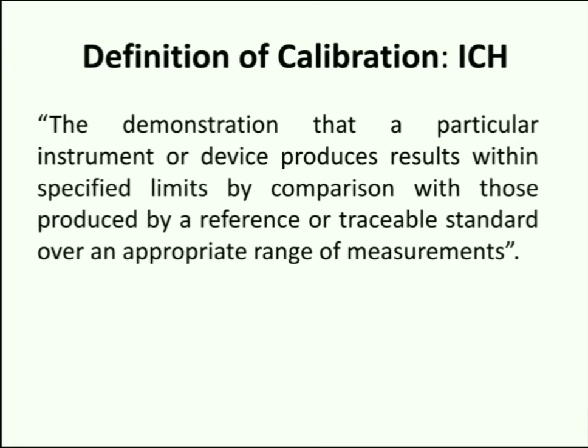So according to ICH, calibration is the demonstration that a particular instrument or device produces results within specified limits by comparison with those produced by a reference or traceable standard over an appropriate range of measurements. This definition means that, according to ICH, calibration is the demonstration of whether a particular instrument or device produces results within the specified limits or not. Also, the data obtained is verified by comparison with the data from a reference standard within an appropriate range of measurements.